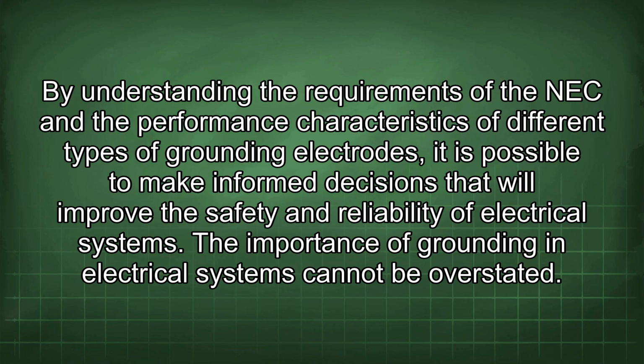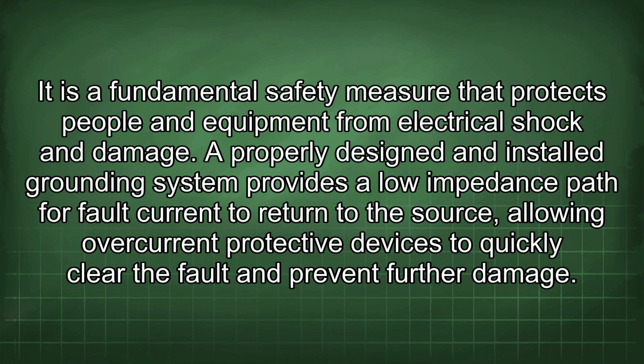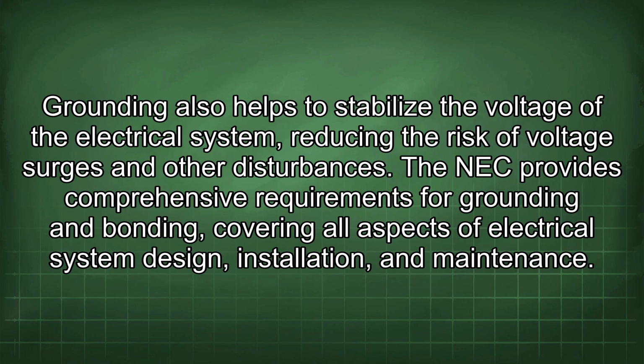The importance of grounding in electrical systems cannot be overstated. It is a fundamental safety measure that protects people and equipment from electrical shock and damage. A properly designed and installed grounding system provides a low impedance path for fault current to return to the source, allowing overcurrent protective devices to quickly clear the fault and prevent further damage. Grounding also helps to stabilize the voltage of the electrical system, reducing the risk of voltage surges and other disturbances.